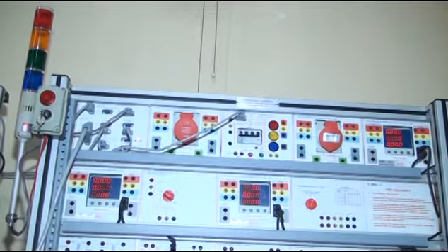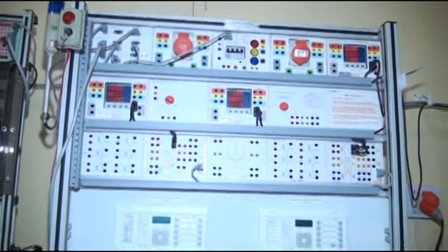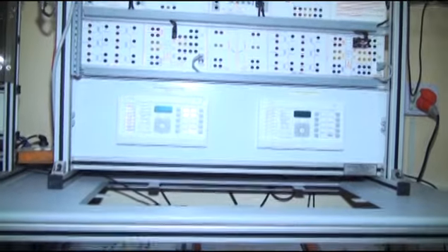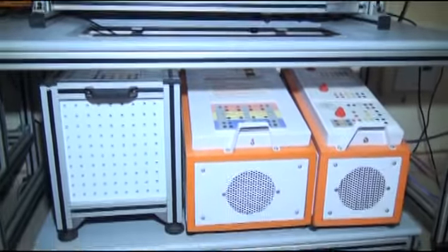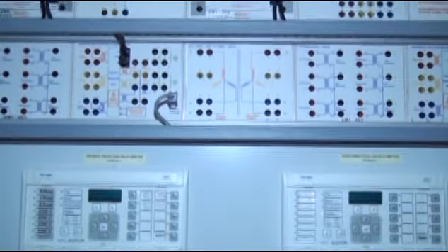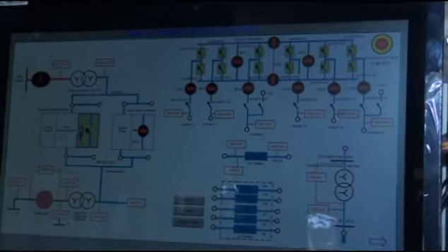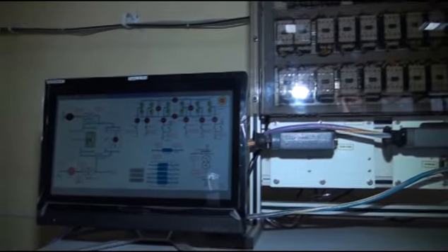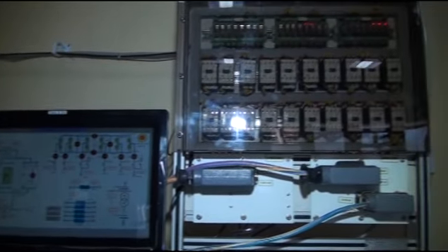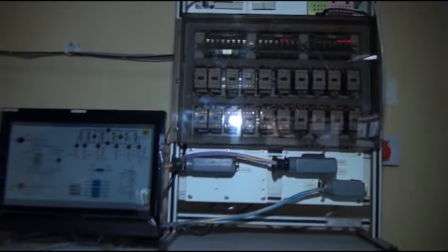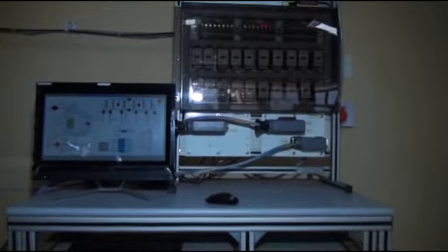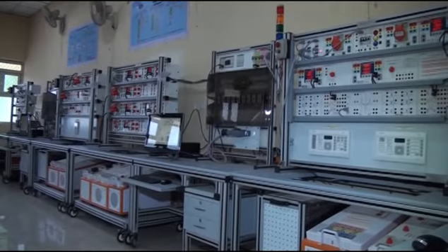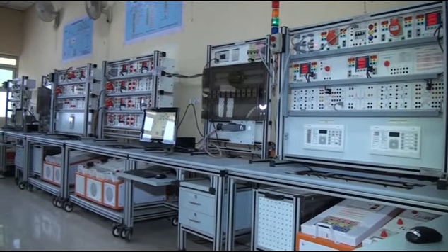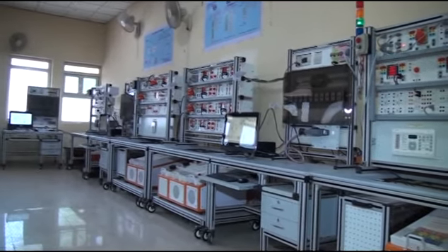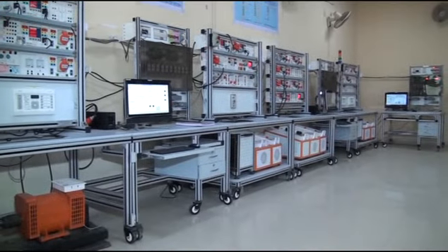This is the transmission and distribution setup consisting of Alstom MiCOM transformer protection relay, distance protection relay, distribution transformer, and transmission lines of 120 km to 50 km with signal tower for indication. All 3 RTUs, 3 HMIs and 1 master HMI, that is the PC, are connected in a network through an Ethernet switch placed near the master HMI. All IEDs, intelligent electronic devices like relays, energy meters and VFDs, are connected over RS485 bus to the RTU.